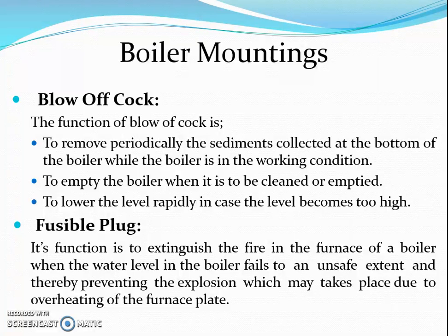Next is the blow off cock. The function of the blow off cock is to periodically remove the sediments collected at the bottom of the boiler when the boiler is in working condition. You can also use it to empty the boiler when it is to be cleaned, and to lower the level rapidly in case the level becomes too high.